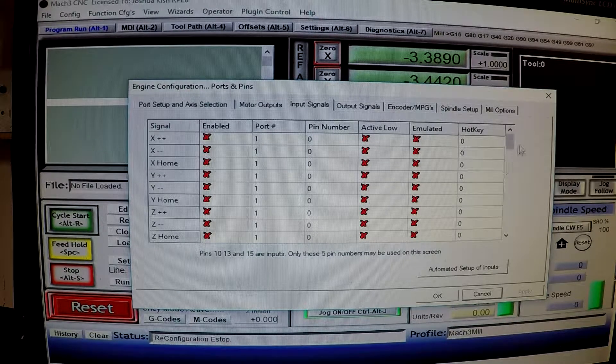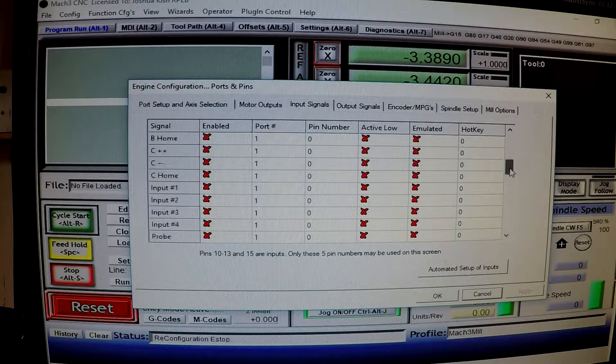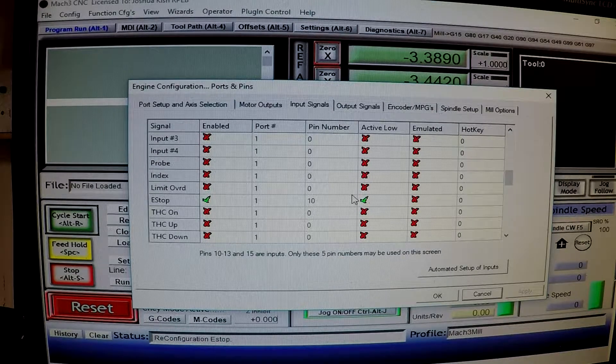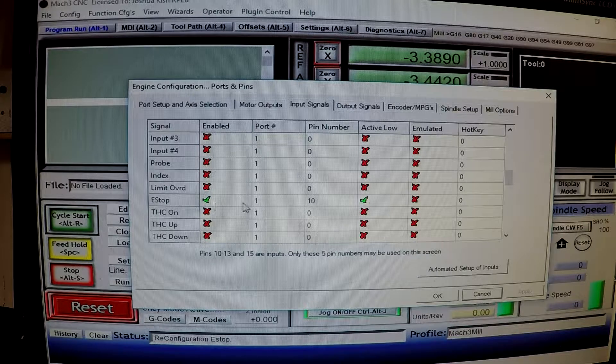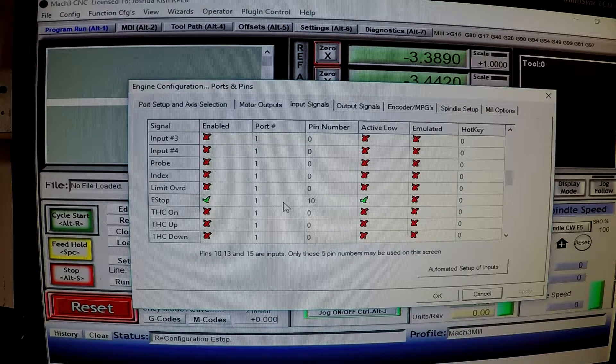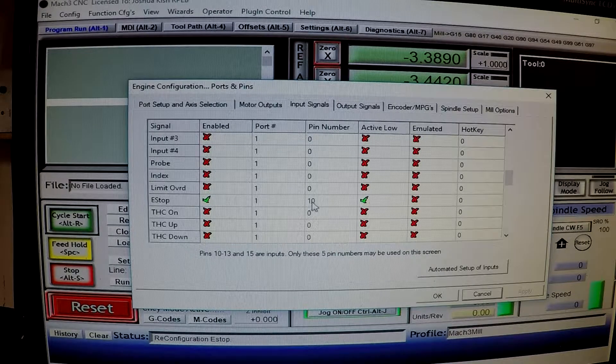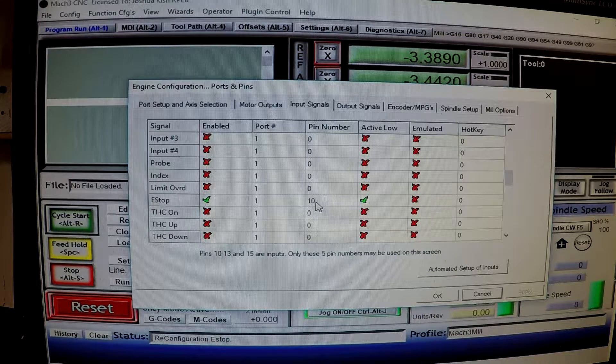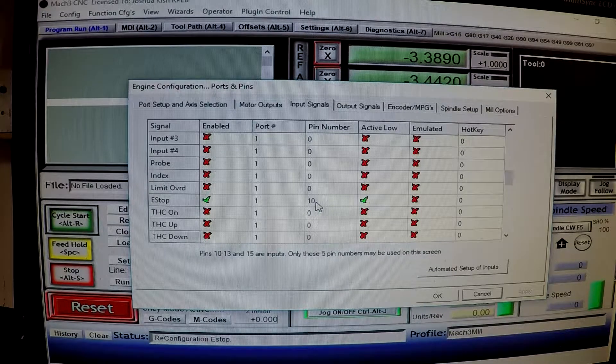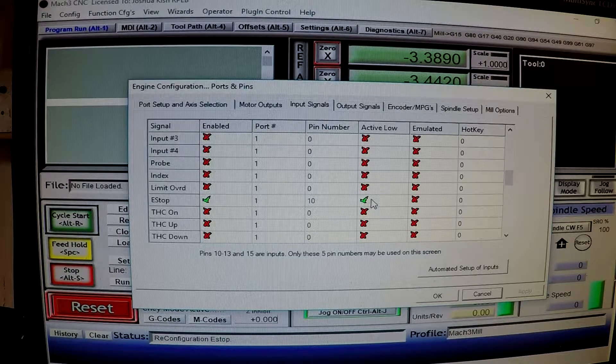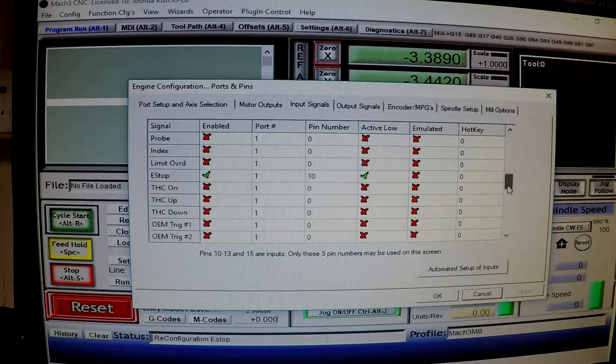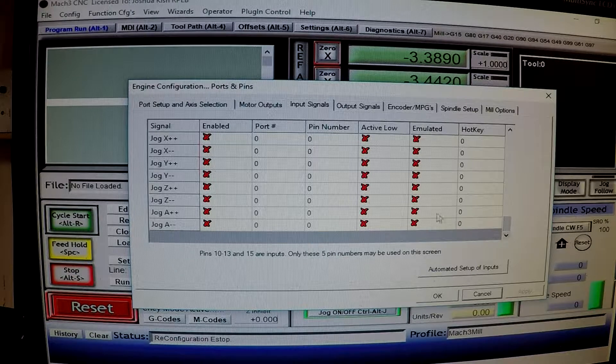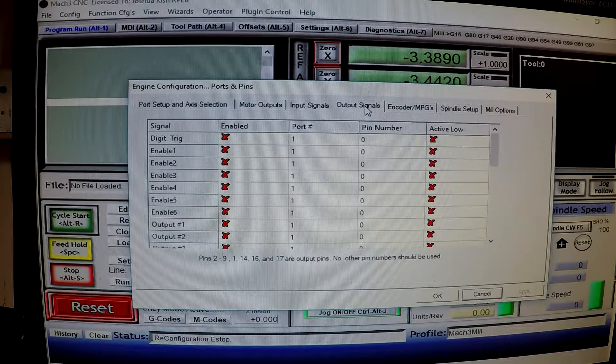Going to input signals. I don't think anything is activated here. Possibly the E stop. Yep. It's got the E stop. That is checked. Port number 1. Pin number 10. You guys saw that earlier on the little schematic I had. And also on the board. Active low is checked on. And that's pretty much it.